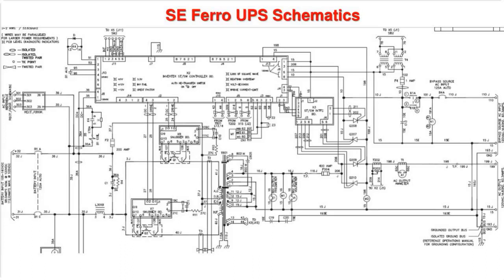And then that goes out. Once again, our sine wave goes out, and we have this T202, which is a CT monitoring the current out of the system, and it reports back to this control board here, which is monitoring the output current of the system. If the output current gets too high, and if the bypass is available, it will tell the system to transfer to bypass and clear the fault, because we don't want to clear faults with the inverter if we have bypass available. And then our load circuits are connected here.